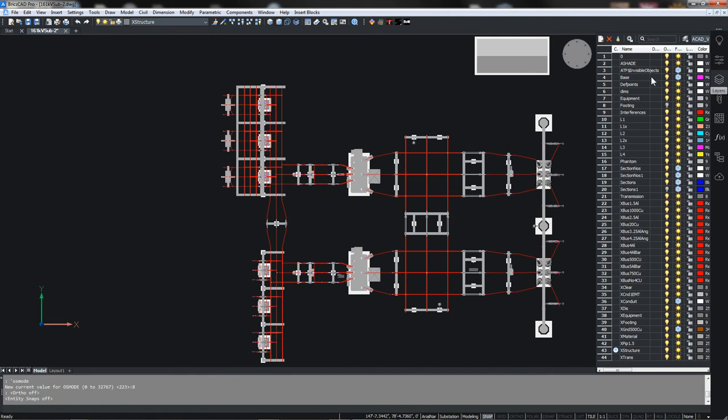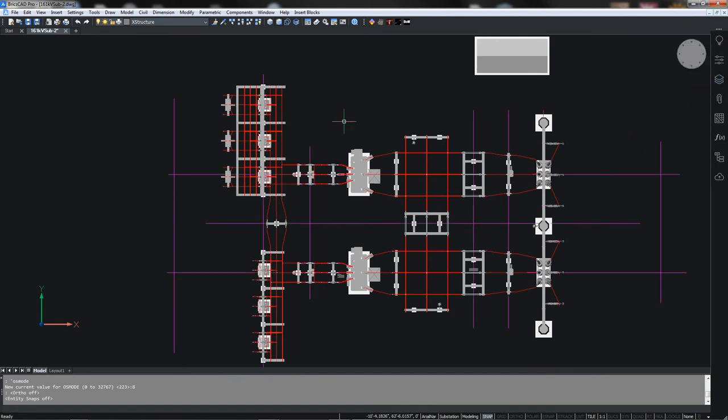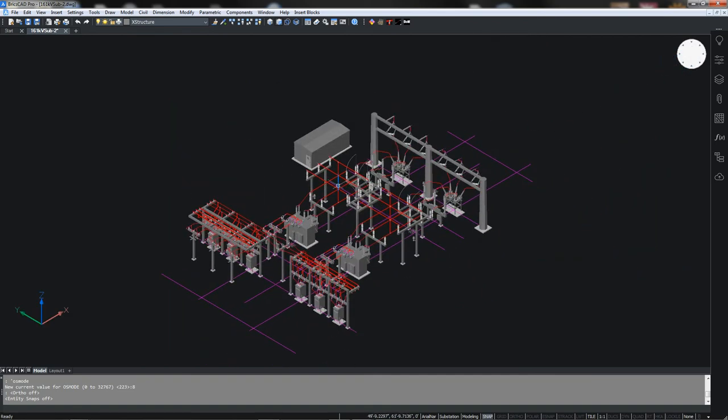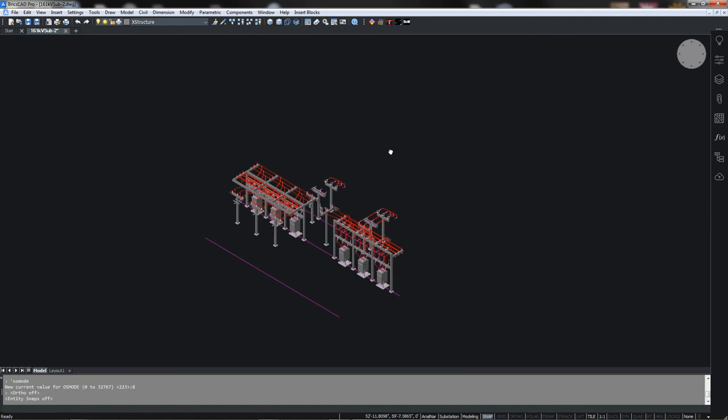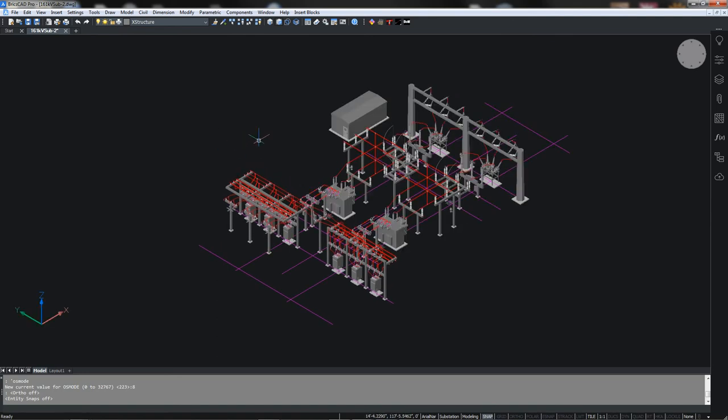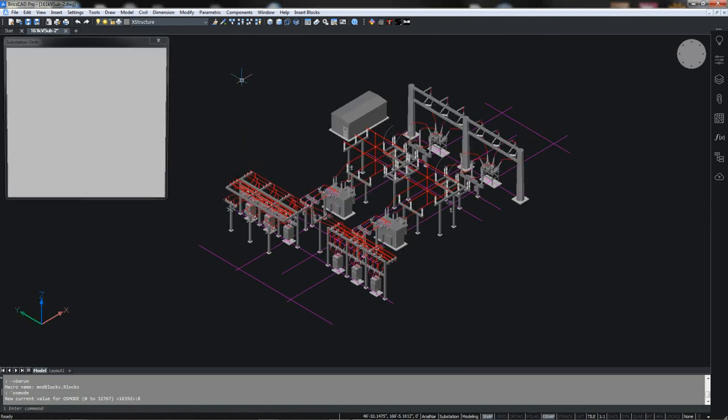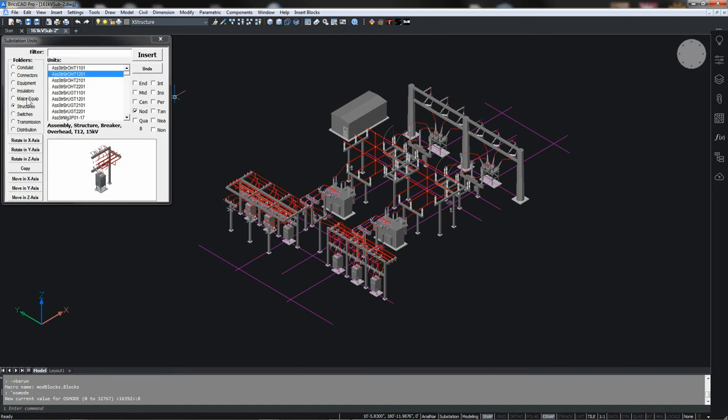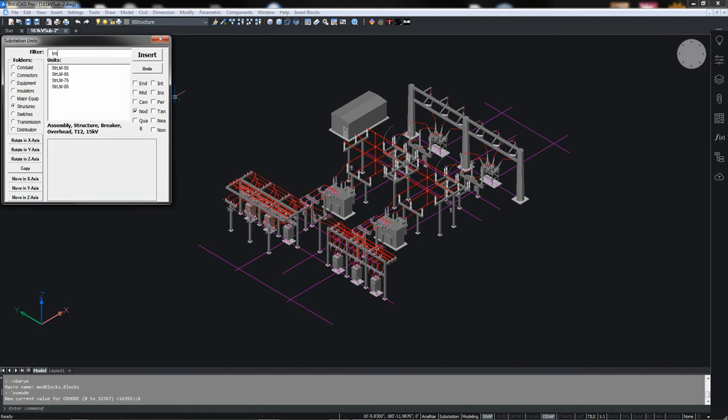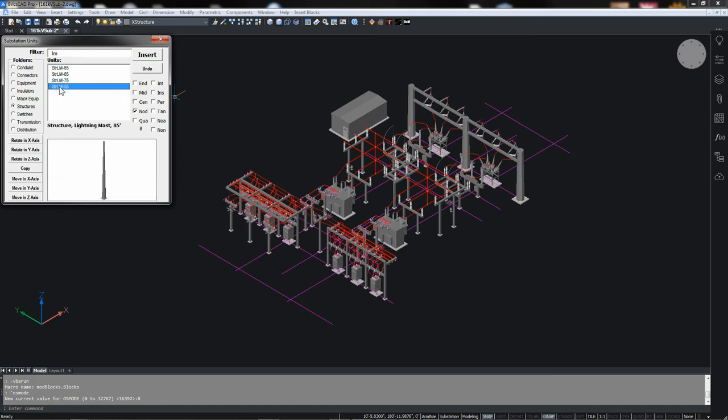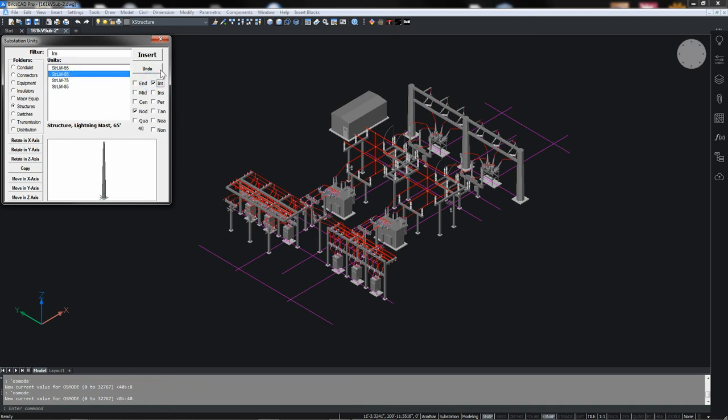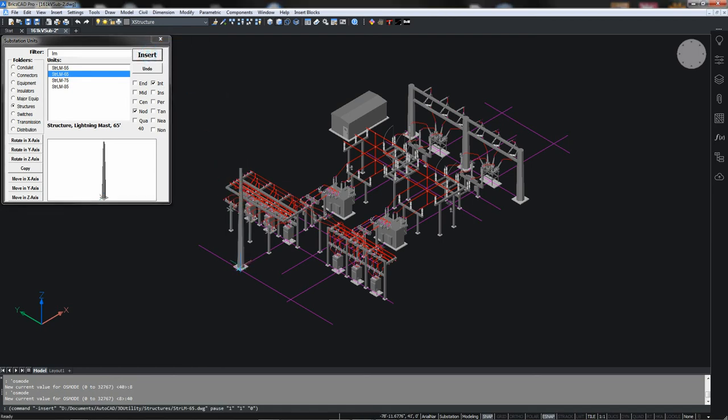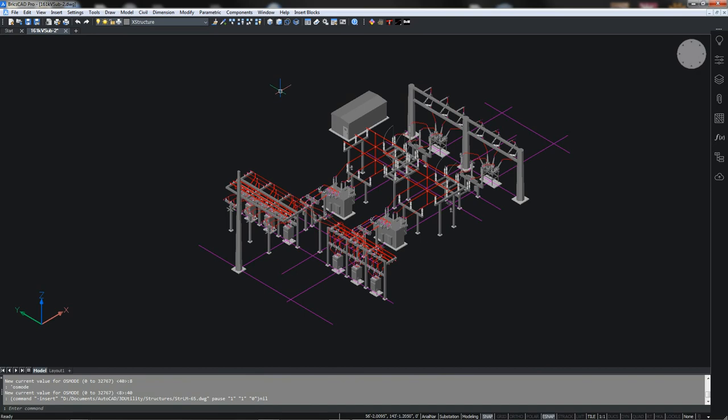First I want to turn on this layer that I've used in the past as layout lines to help locate items in the substation. Let's go to our ortho view here where we can begin our design. The first thing I want to do is pull up our 3D toolbox and here in the structure section I want to select a lightning mast. We've got a selection of lightning masts from 55 to 85 feet. For this design 65 will be the size we need, so I'll select the intersection snap point and insert our lightning mast.